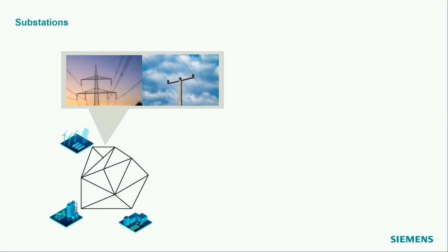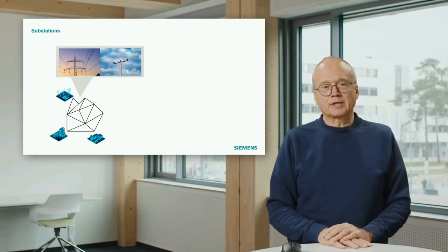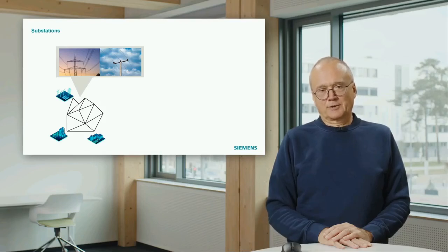On the tower on the left-hand side, for instance, you see 2 systems, 2 times the 3 phases. What you also see is a so-called earth wire on top of the tower. This earth wire does not normally transport any energy. The reason for the earth wire is that it is a lightning protection for the line, and nowadays it often also carries optical fibers for communication.